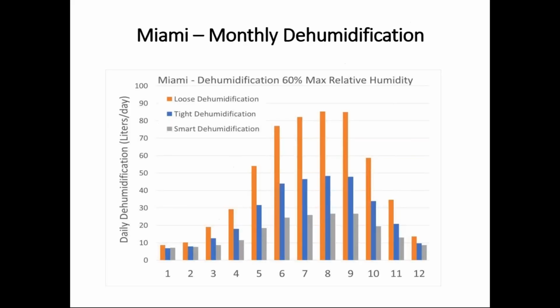Finally, let's look at some characteristics over the course of the year, and we'll use Miami because it's ground zero for dehumidification. Key West, maybe a little more. We also have modeled San Salvador, where we've been involved in a project. So there's more moist areas in the world, but this is right up there. In looking at loose, tight, and smart, you can see on a monthly basis from January, month one, to December, it peaks around July, August, September, as you'd expect. And from our hand calculation, we're at about 90 liters per day, 92, 94.